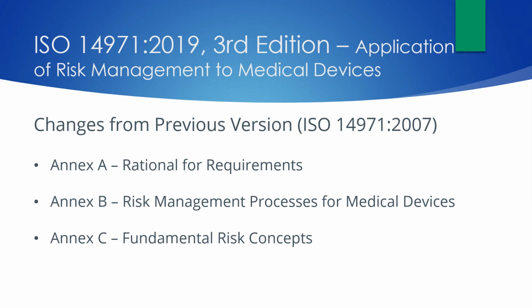The updated ISO 14971 also has changes to the annexes. Annex A is the rationale for the requirements. Annex B, which is the risk management processes for medical devices, provides detailed correspondence between the 2007 version and the 2019 version, including a graphic reflecting the changes. I would highly suggest any organization that's looking to transition to the new standard review Annex B to be able to complete their gap analysis effectively. Annex C, Fundamental Risk Concepts, includes a graphic that depicts the relationships of hazard, sequence of events, hazardous situation, and harm that was previously in Annex E.1.